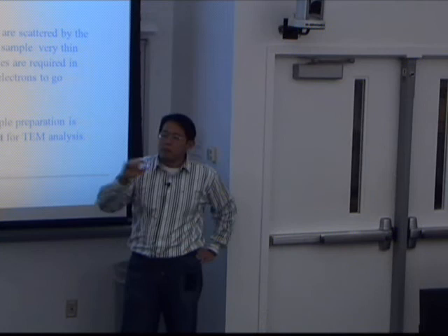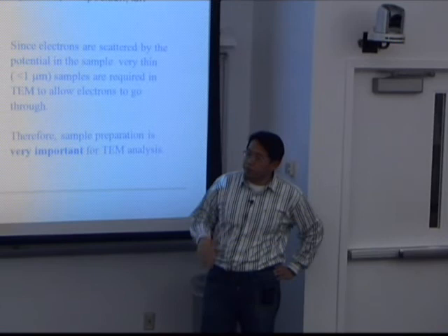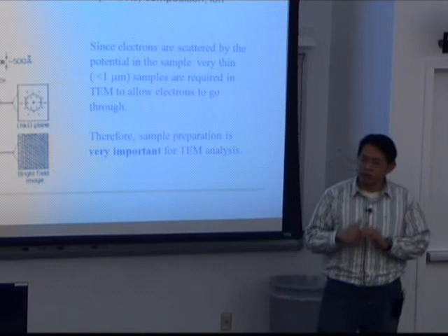The third limitation: TEM is very time-consuming for sample preparation. You want electrons to transmit through the sample, so you need to make a very thin sample. Thinner is better — thinner gives better resolution. Typically, if you want high-resolution TEM, you want to reduce the sample thickness to 50 nanometers, which is very challenging. We will talk more about sample preparation in the next class. In any case, you want the sample thinner than one micron to allow electron transmission.